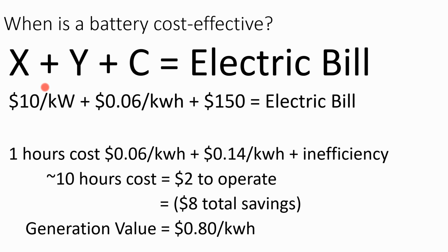But if my demand charge is $10 a kilowatt, and let's say I'm hitting my facility's peak demand for 10 hours a month, I have to run that battery for 10 hours a month to reduce the peak demand. So 10 hours times 20 cents a kilowatt hour, it costs about $2 to run my battery, but I save $10 because I'm hitting that peak demand for 10 hours a month.